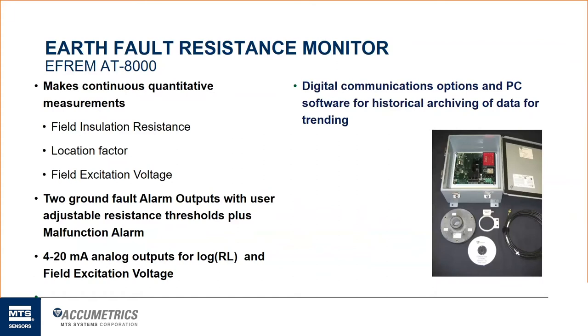We also offer a malfunction alarm. Again, the two ground fault alarm thresholds and the malfunction alarm are those Form C contact relays, normally open, normally closed. The malfunction alarm is a normally closed contact. The reason we do that is because if the EFREM system loses power, it will open that alarm and let them know that there is a problem in the telemetry system. We also offer 4 to 20 milliamp analog outputs, two channels. Channel one is for the field resistance that they can trend that historical information over time. And channel two is the field voltage. So many utilities use that feature. They interface that into their control room and they're looking at that 4 to 20 current loop signal. And once it falls below a certain threshold, maybe 8 milliamps, 9 milliamps, something like that, they need to start paying closer attention because they're trending towards that ground fault.